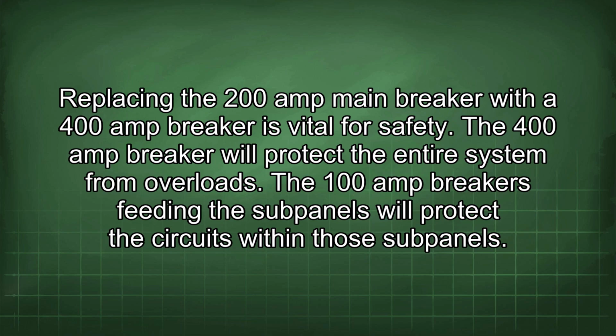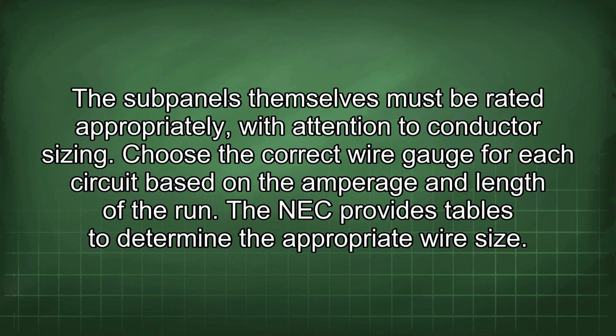Replacing the 200-amp main breaker with a 400-amp breaker is vital for safety. The 400-amp breaker will protect the entire system from overloads. The 100-amp breakers feeding the subpanels will protect the circuits within those subpanels. The subpanels themselves must be rated appropriately with attention to conductor sizing. Choose the correct wire gauge for each circuit based on the amperage and length of the run. The NEC provides tables to determine the appropriate wire size.